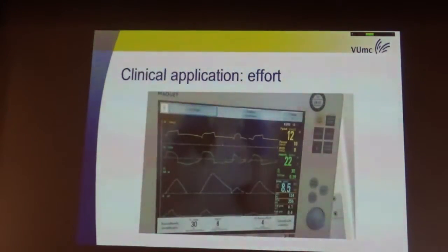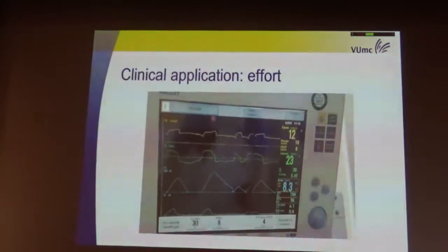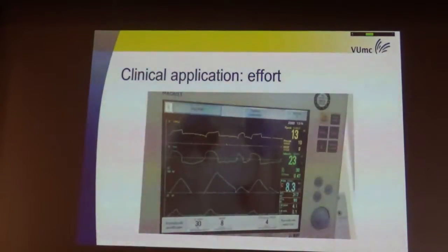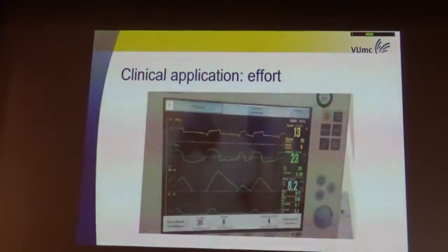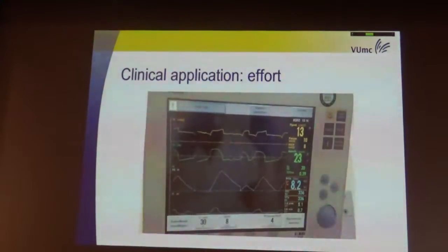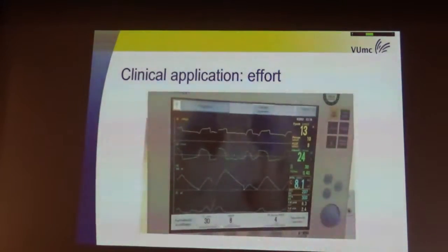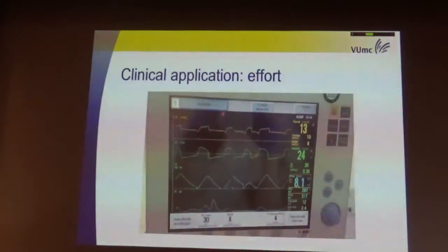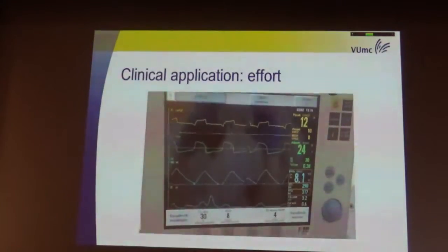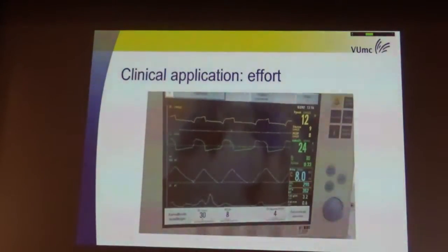And the only thing I did right now is reduce the level of inspiratory support to 4, and there is activity of the diaphragm. So even though it doesn't allow you exact quantification of the effort, the signal will tell you that this patient at 8 of pressure support was in over-assist.